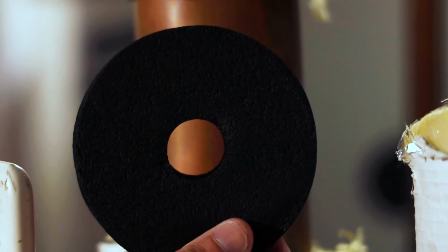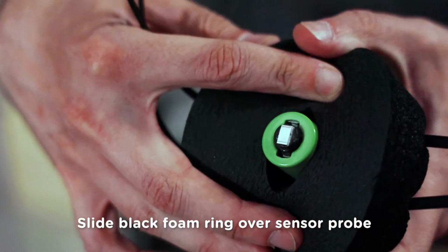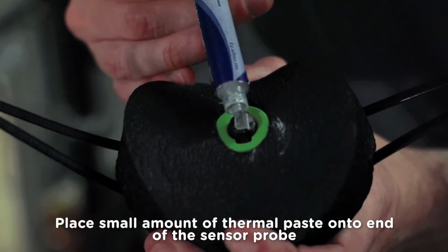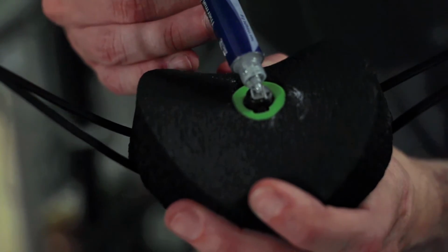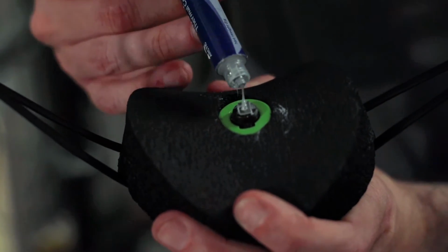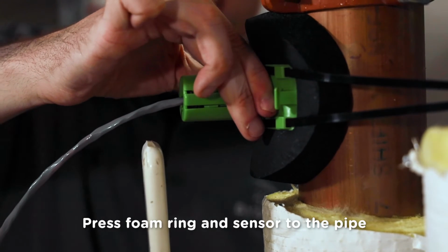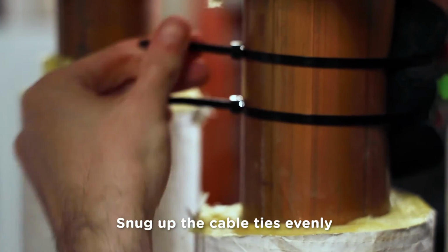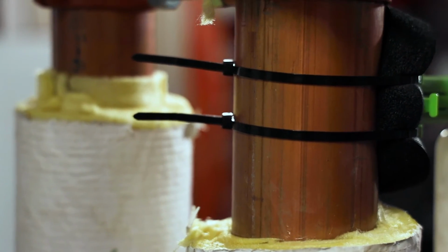Inside the box, you'll find a black foam ring that looks like a donut. Just slide that ring over the green sensor probe. Apply the thermal paste to the end of the sensor. Again, use a small amount and don't skip this step. Press the foam ring and temperature sensor onto the pipe and snug up the cable ties so the sensor sits firmly at a 90 degree angle.